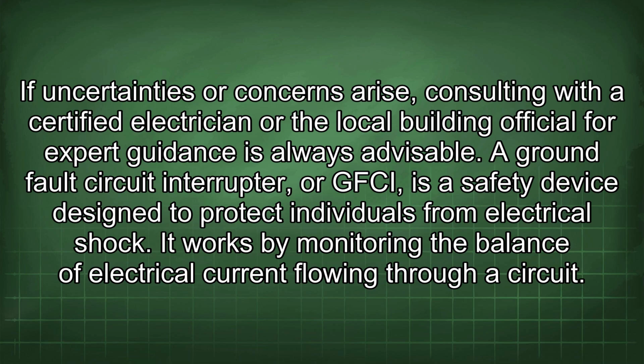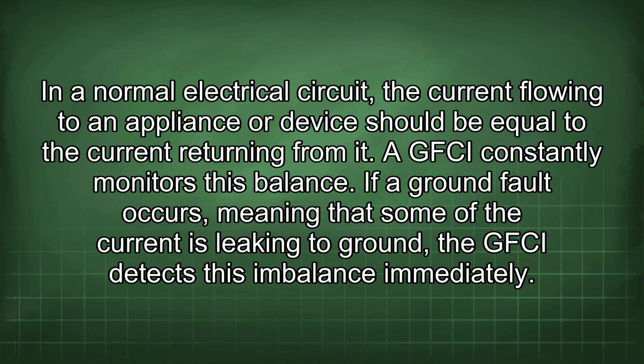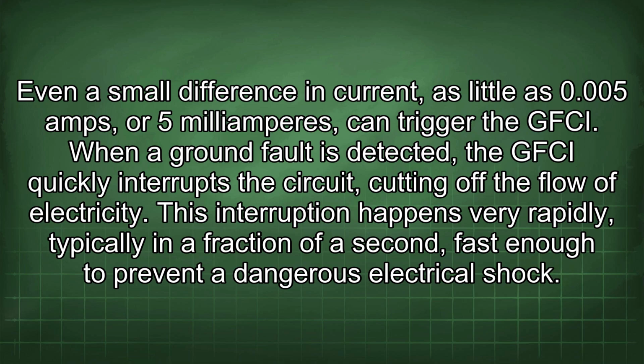A ground fault circuit interrupter, or GFCI, is a safety device designed to protect individuals from electrical shock. It works by monitoring the balance of electrical current flowing through a circuit. In a normal electrical circuit, the current flowing to an appliance or device should be equal to the current returning from it. A GFCI constantly monitors this balance. If a ground fault occurs, meaning that some of the current is leaking to ground, the GFCI detects this imbalance immediately. Even a small difference in current, as little as 5 milliamperes, can trigger the GFCI. When a ground fault is detected, the GFCI quickly interrupts the circuit, cutting off the flow of electricity. This interruption happens very rapidly, typically in a fraction of a second, fast enough to prevent a dangerous electrical shock.